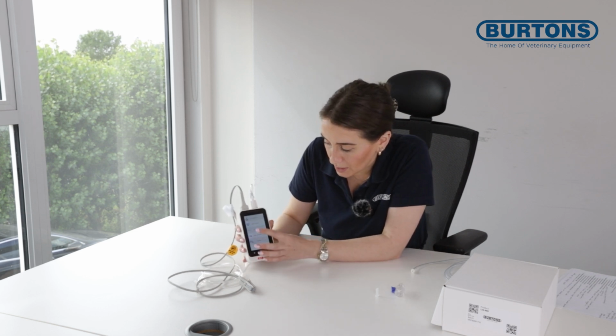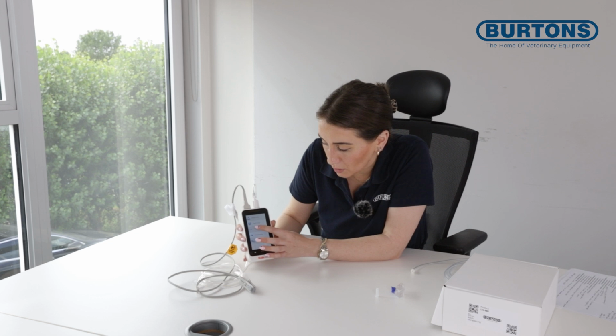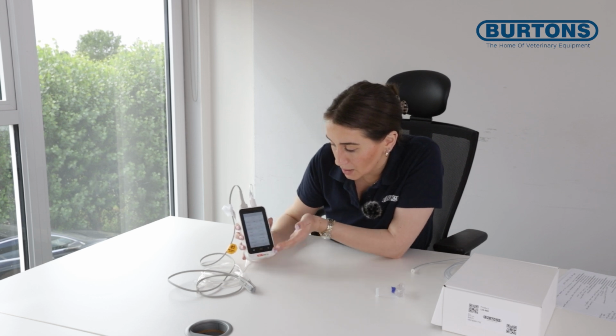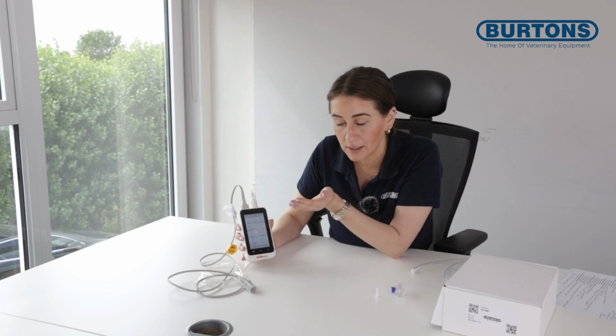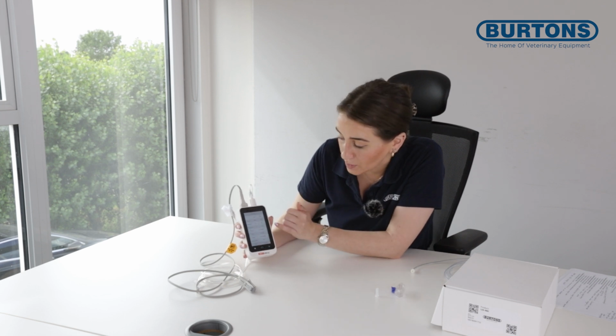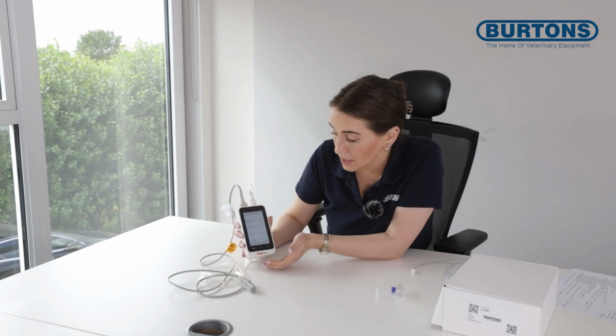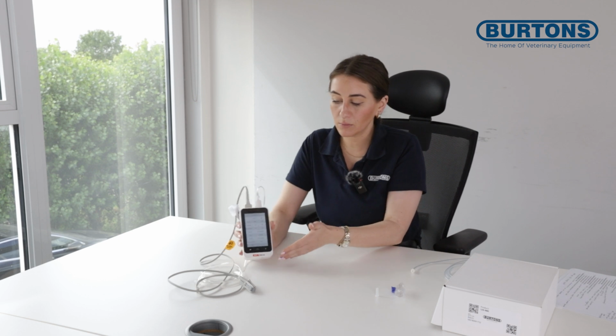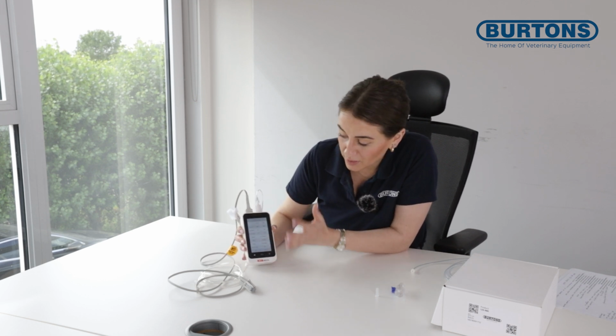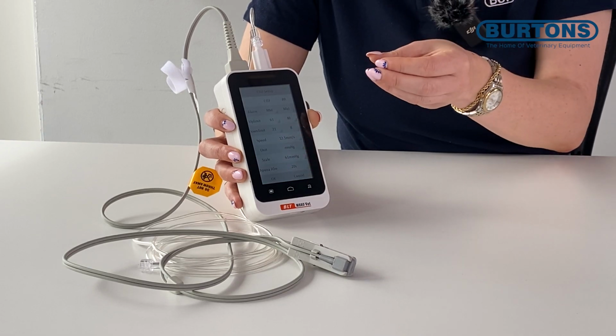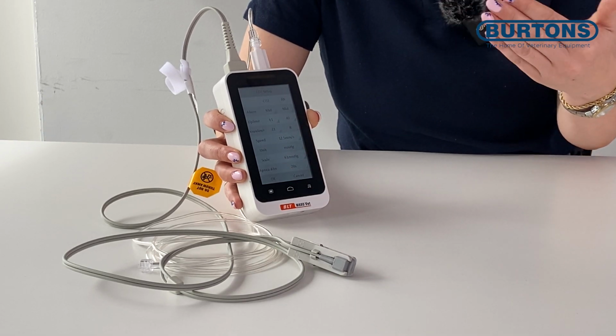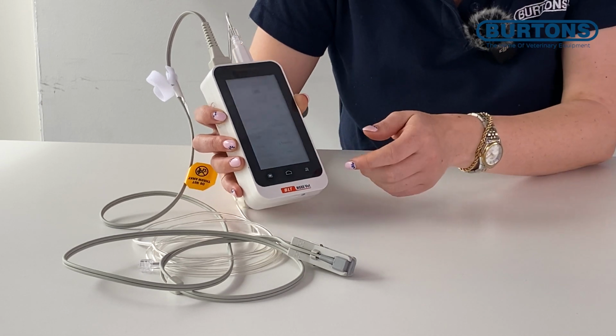We can go in here and go into CO2 setup, and similarly we can alter anything that we need to. So we can alter the higher end tidal CO2, lower end tidal CO2, and we can also alter respiratory rate. So the other option that we have with the machine is to alter the sweep, and that's referring to the speed, that's referring to the representation of the graph compared with time. So for example, if I want to see more in a smaller screen, I can change that, or if I want to see less and have more detail, I can also alter that within these settings.